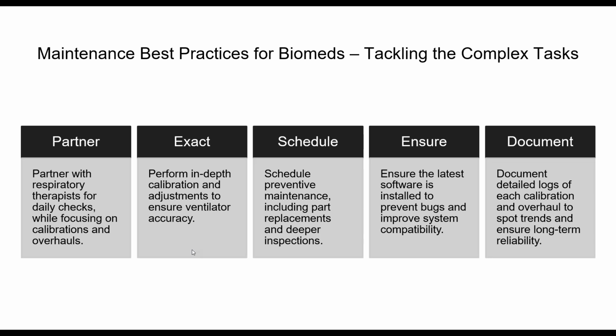They would bug it, we'd go back and tell them what we found, then we'd replace it with a good part. They partnered people with ventilator experience with people without, or limited experience. My partner would go get the new component, we'd put it in, and we'd leave the room, and then they'd bug our system again. On the second, third, and even fourth time we came in, I said there's two problems going on with this ventilator, because I had been checking the other components, not just pressure and stopping there, or not just volume and stopping there.